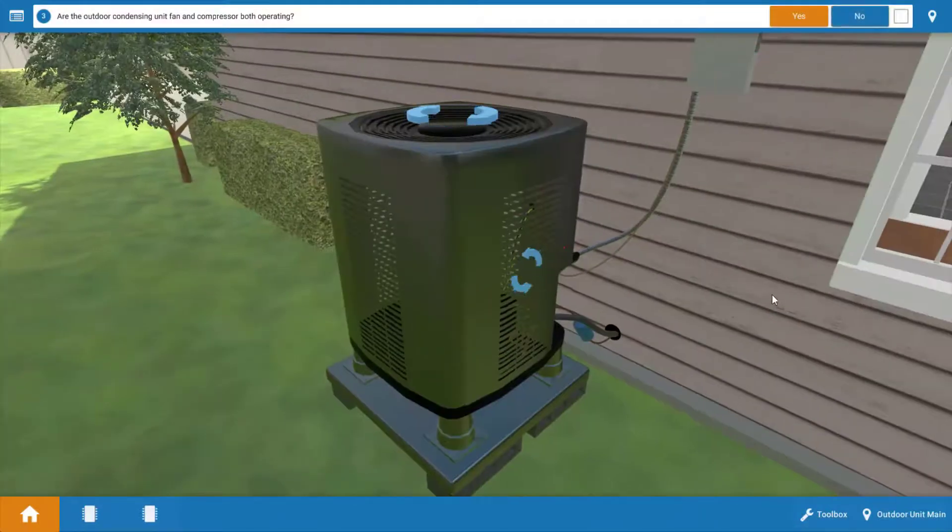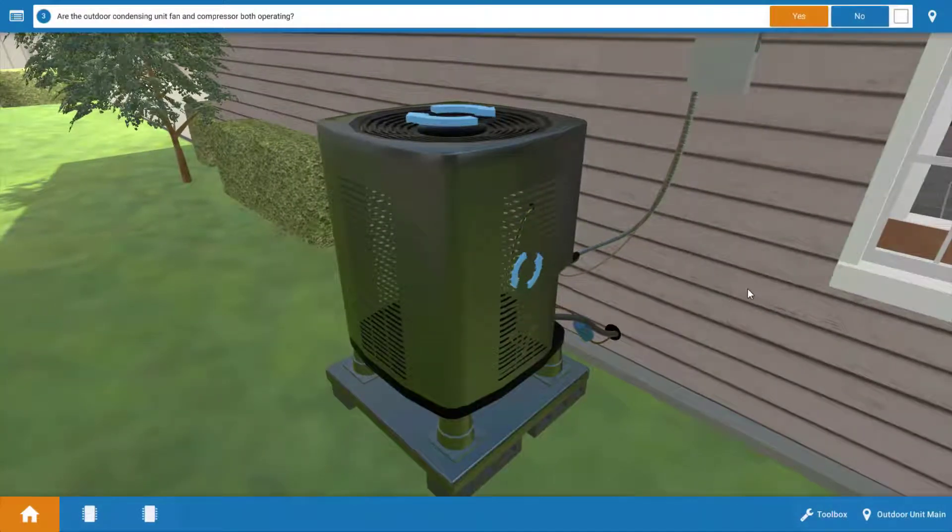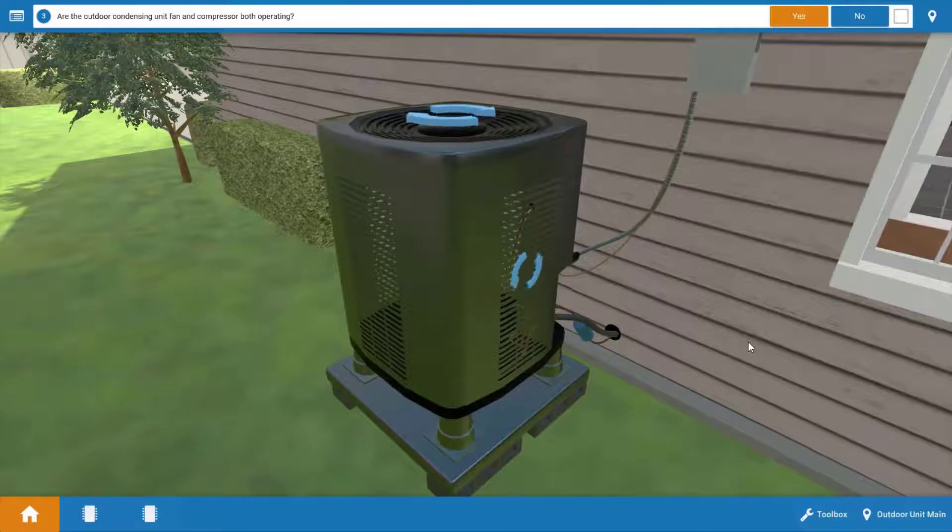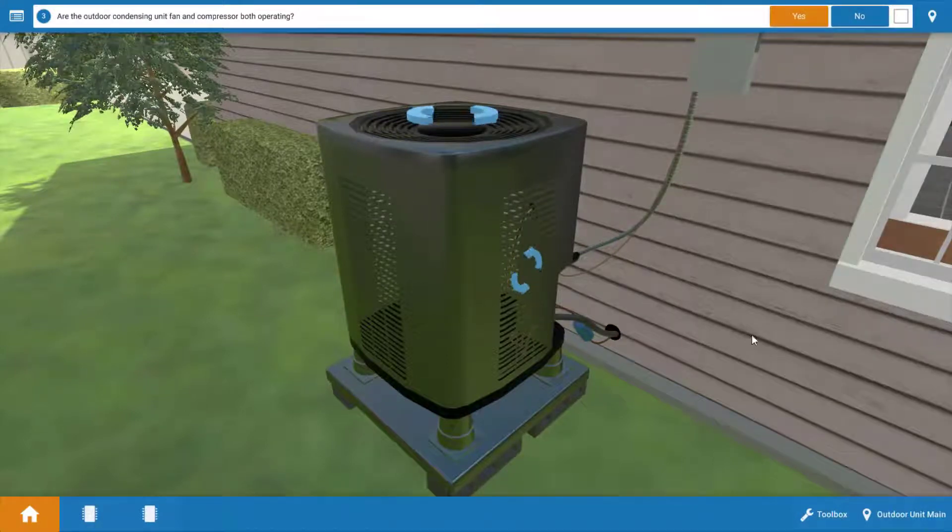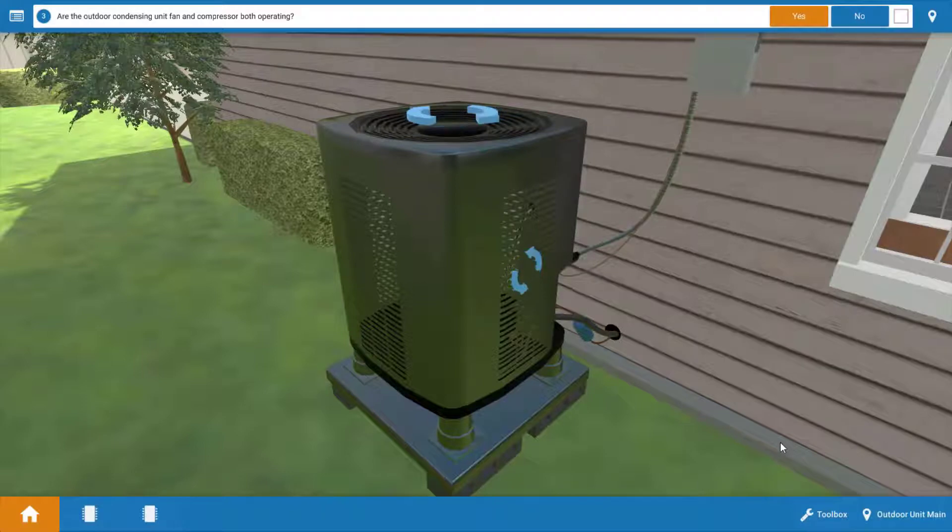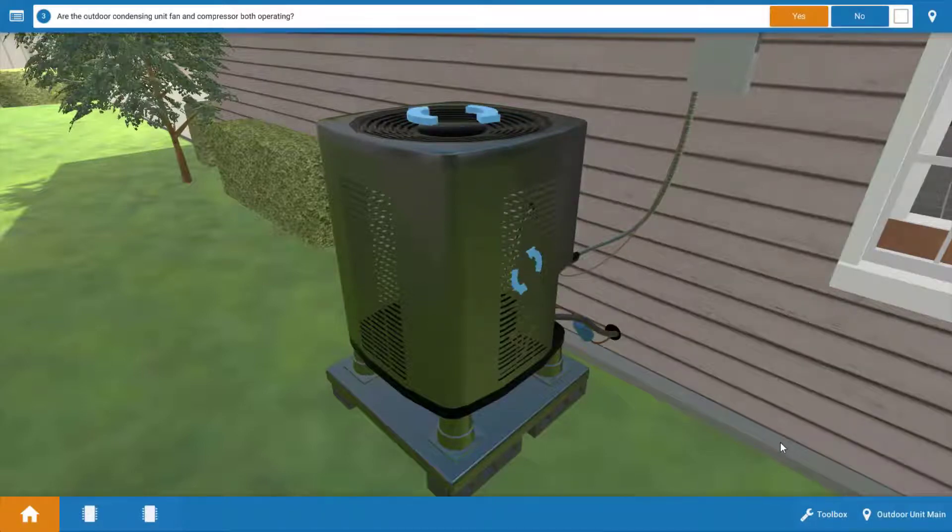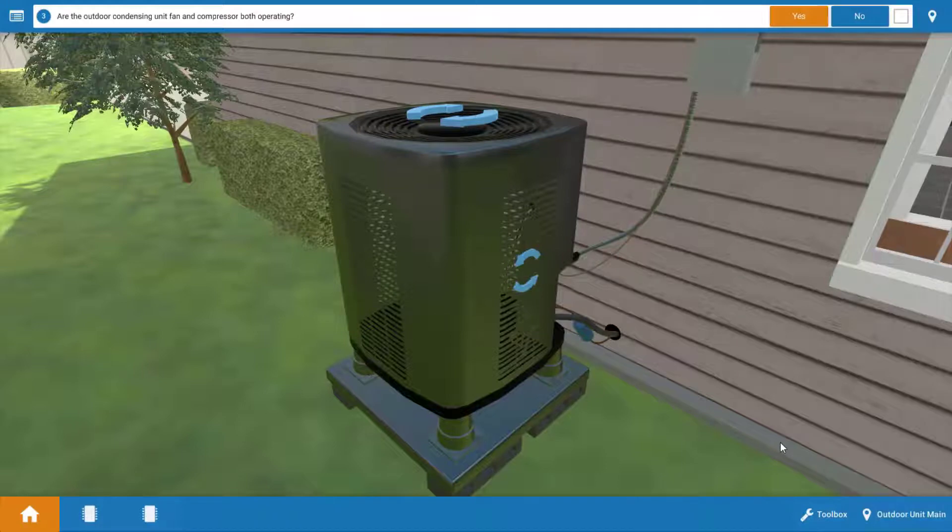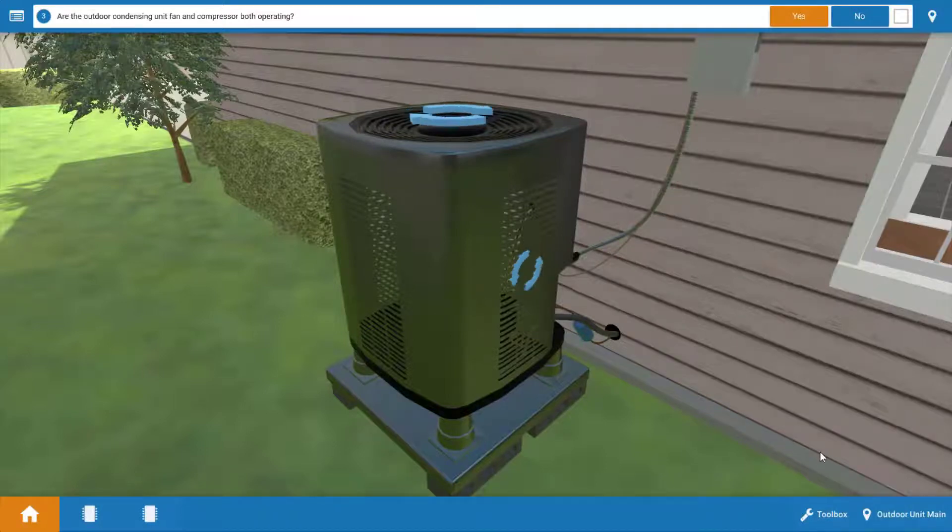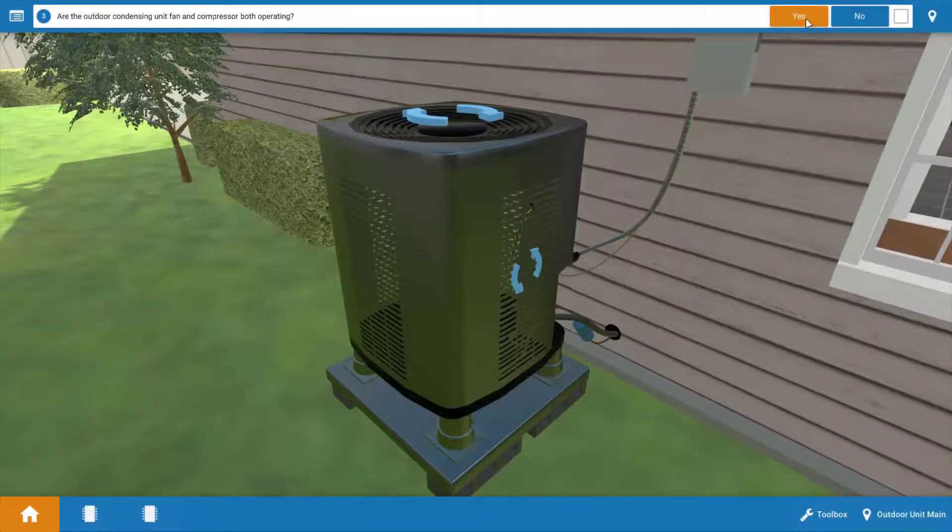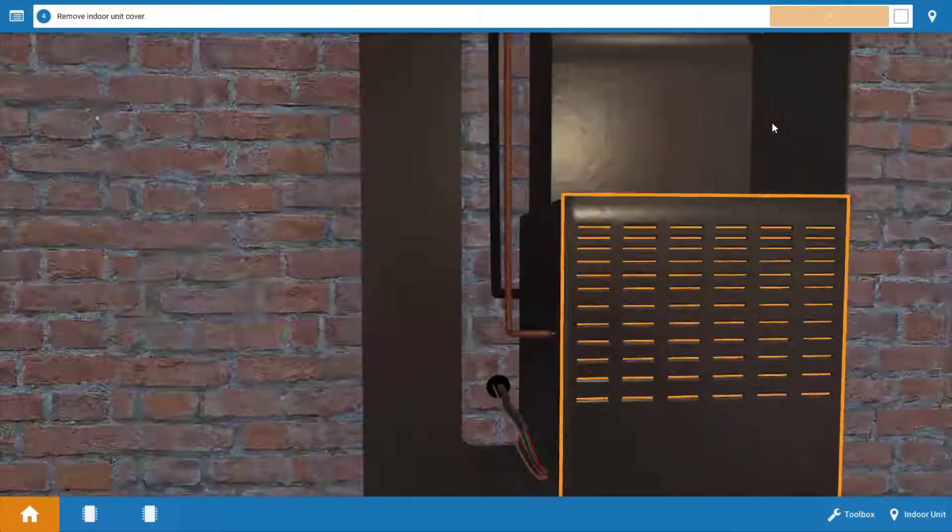Now we go to the outdoor unit, and we can see that both the compressor and condenser fan motor are in fact running. Now, if this problem is allowed to persist for quite some time, this could result in severe icing of the coil, as well as the unit possibly cycling off on a low pressure switch if it has one. So we're going to say both loads are running outside.